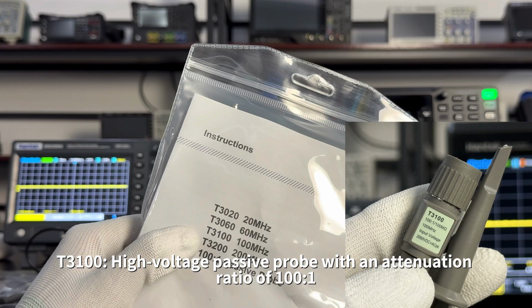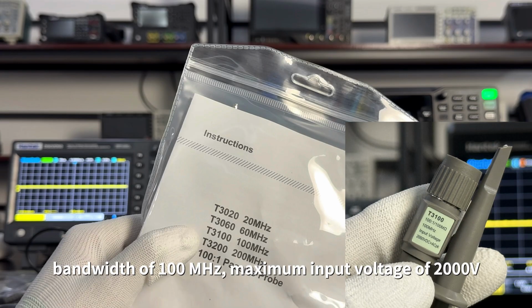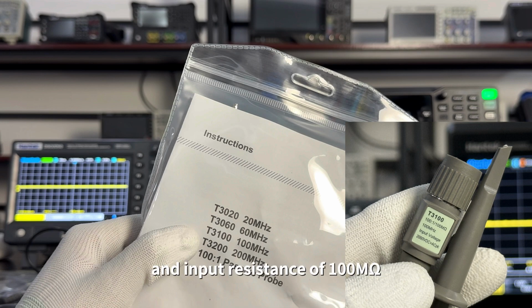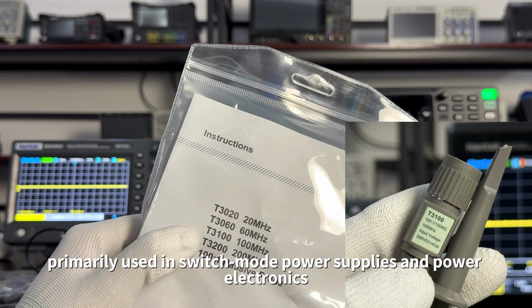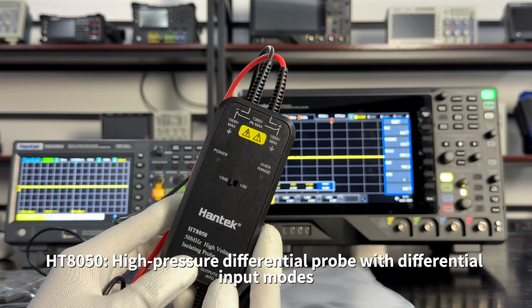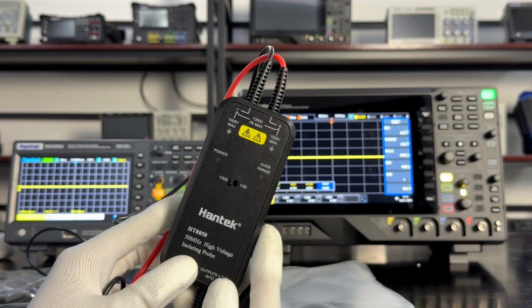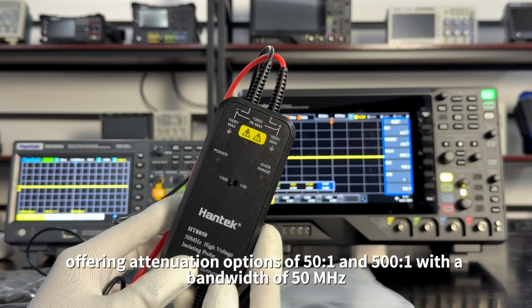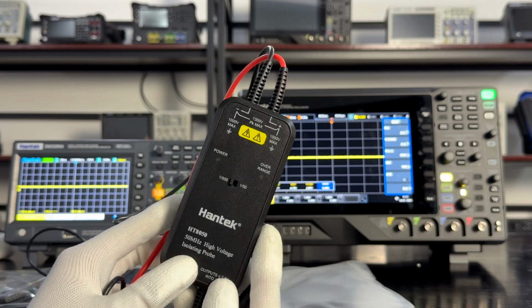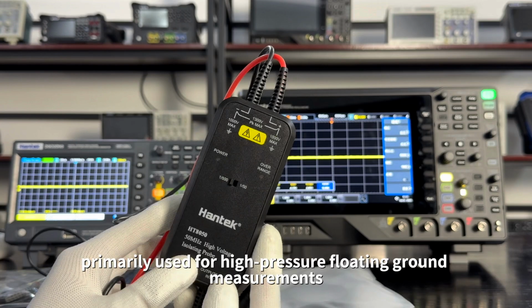T3100, high voltage passive probe with an attenuation ratio of 100:1, bandwidth of 100 MHz, maximum input voltage of 2000 volts, and input resistance of 100 megohms, primarily used in switch mode power supplies and power electronics. HT8050, high voltage differential probe with differential input modes, offering attenuation options of 50:1 and 500:1 with a bandwidth of 50 MHz, primarily used for high voltage floating ground measurements.